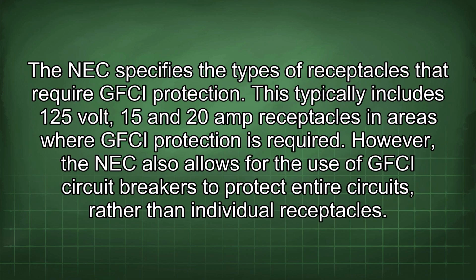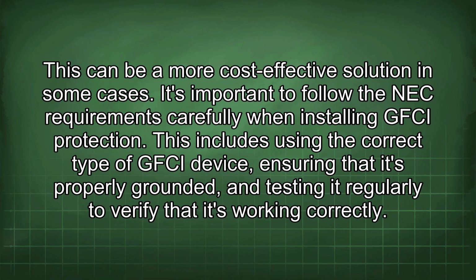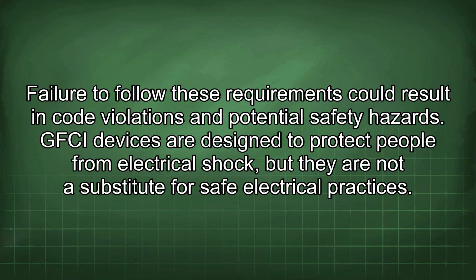The NEC specifies the types of receptacles that require GFCI protection. This typically includes 125-volt, 15 and 20 amp receptacles in areas where GFCI protection is required. However, the NEC also allows for the use of GFCI circuit breakers to protect entire circuits rather than individual receptacles. This can be a more cost-effective solution in some cases. It's important to follow the NEC requirements carefully when installing GFCI protection. This includes using the correct type of GFCI device, ensuring that it's properly grounded, and testing it regularly to verify that it's working correctly. Failure to follow these requirements could result in code violations and potential safety hazards.